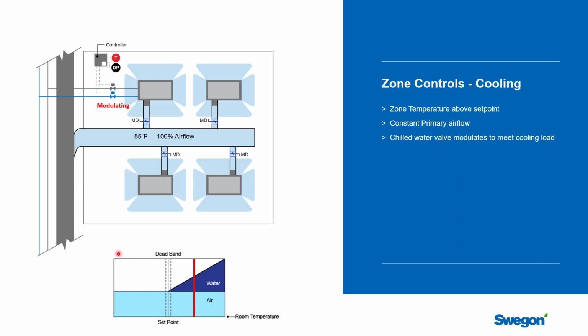If we consider the y-axis here to be the amount of cooling capacity that the system is providing, as long as you're providing 55 degree air to the space, it will do some amount of cooling. And so what's happened as we've moved here is that the air isn't enough to meet the load, and so now we have to run some chilled water through the beams, and as you can see, the more flow we put through it, the more capacity we'll have to meet the load.